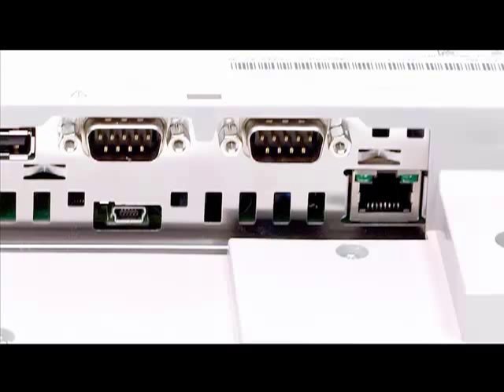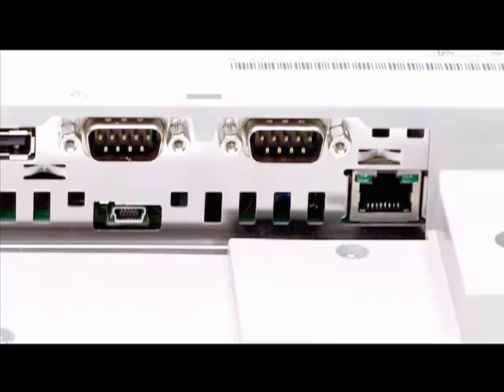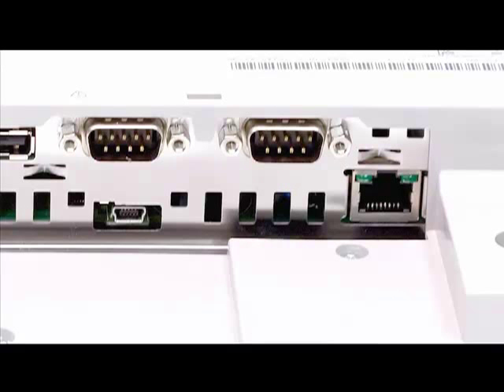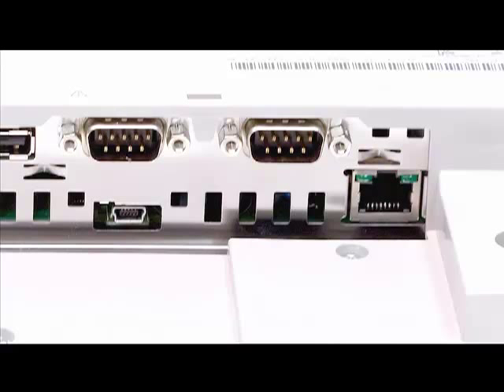Pinouts for the GP4000 series COM ports are different from the AGP3000 series COM ports. Be aware of this when migrating from the AGP3000 to GP4000 series HMIs. To the lower right of COM port 2 is the ethernet port. This is a 10 base T and 100 base T port. This port can be used for program transfer via the PC and GP Pro EX. It is also used for ethernet device connectivity as well as connection to a ProServer EX data management network.